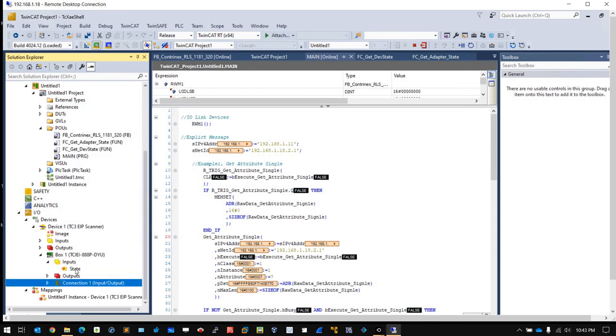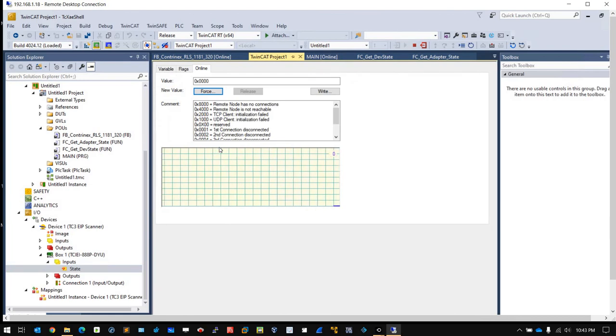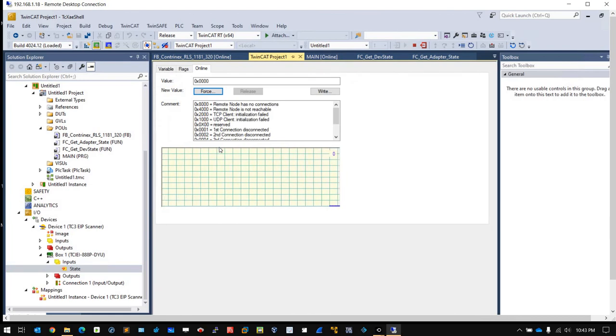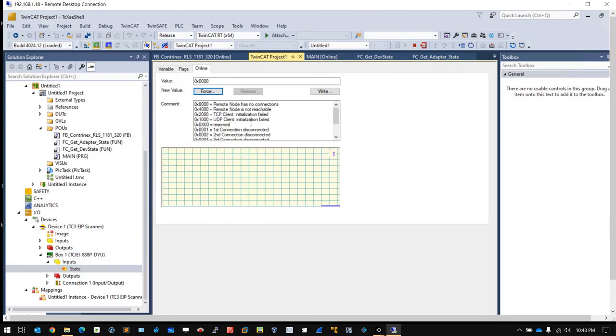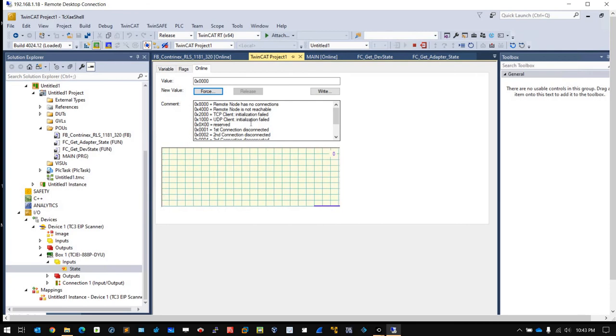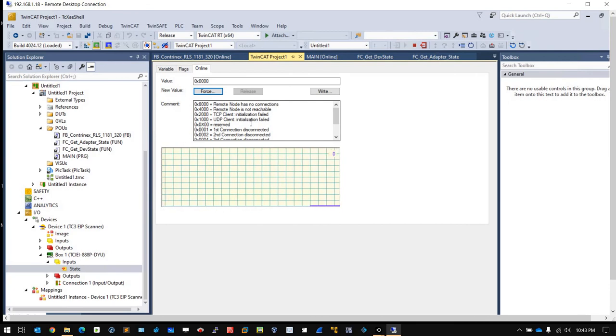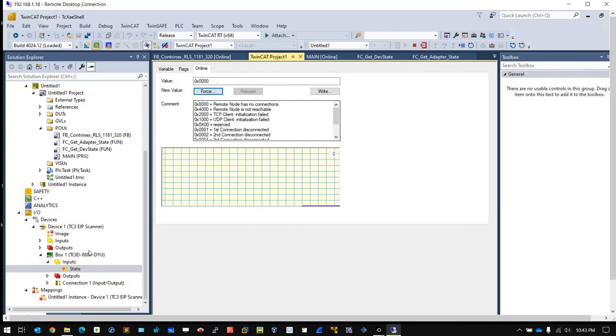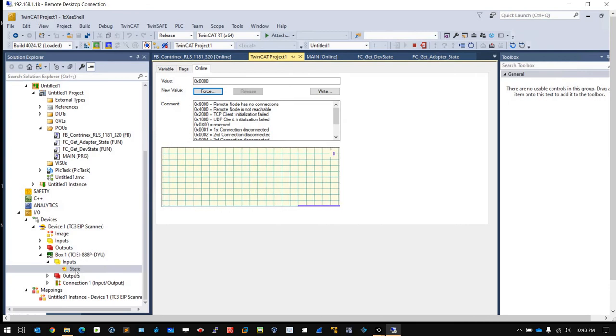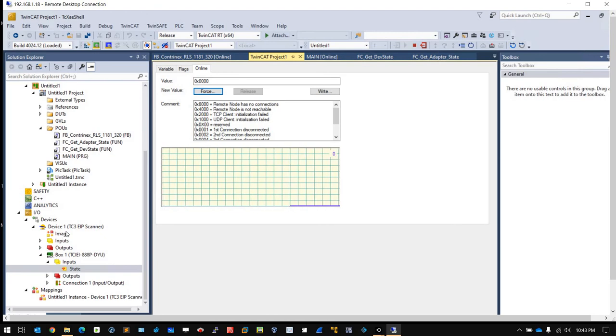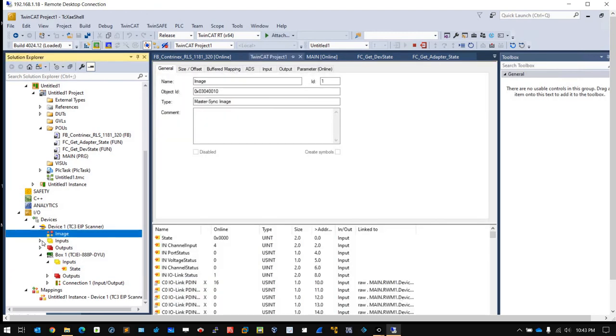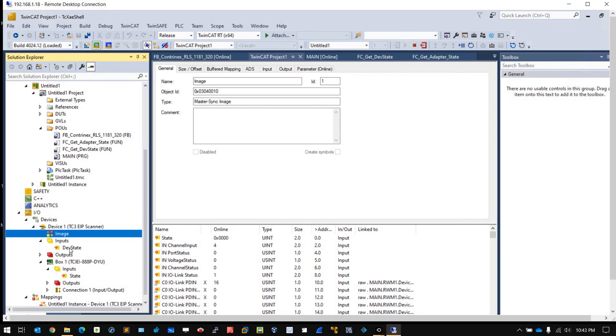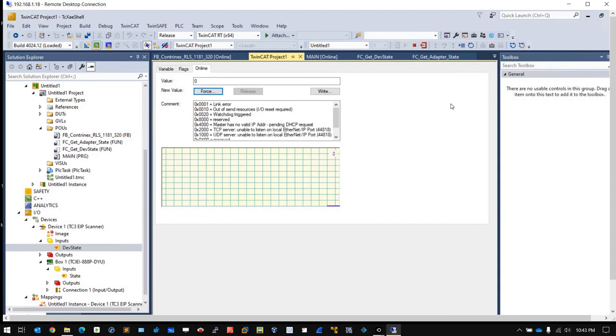Finally, don't forget to check the status when you have problems with communication with your adapter. Don't forget to see the error message on these state variables, and also in the scanner you also get input and device status. It's very useful information for troubleshooting.